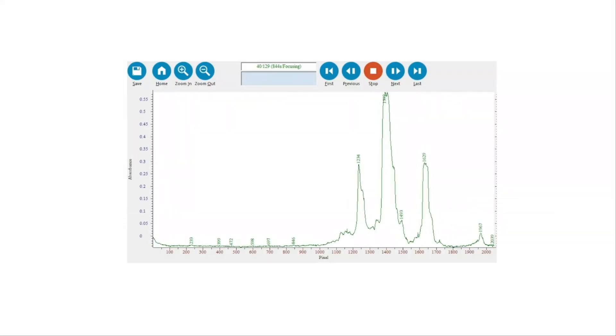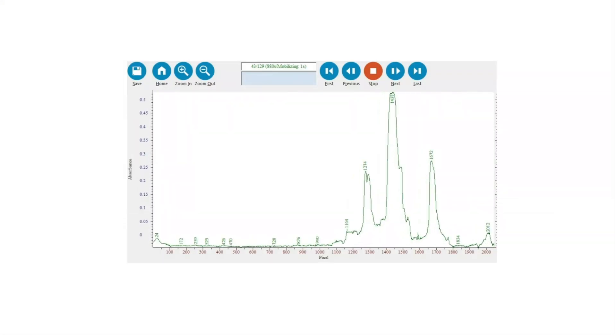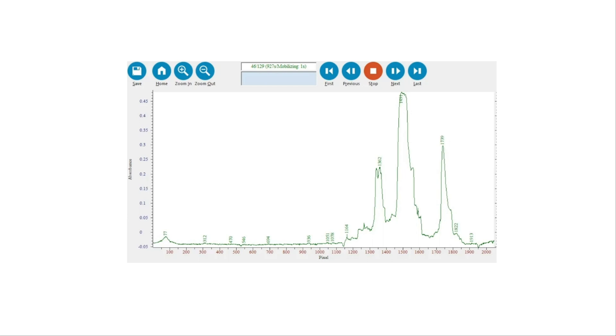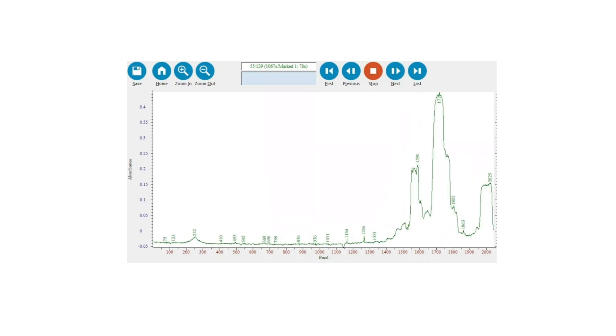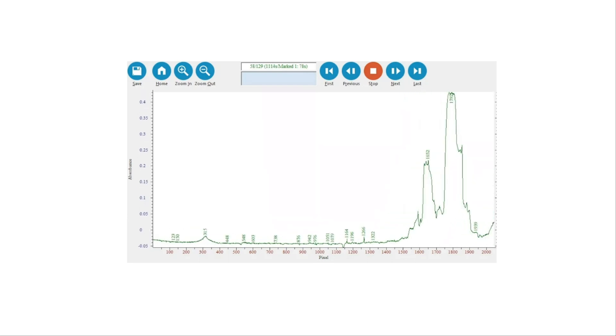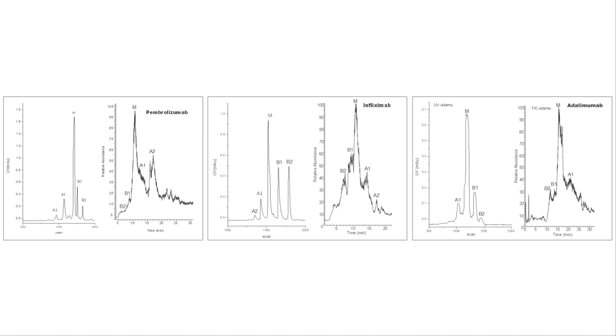Notably, the high resolution of CE-Infinite ICIEF separation is maintained throughout peak mobilization and is transferred to the total ion chromatogram. This allows direct determination of an intact molecular weight for each PI grouping.